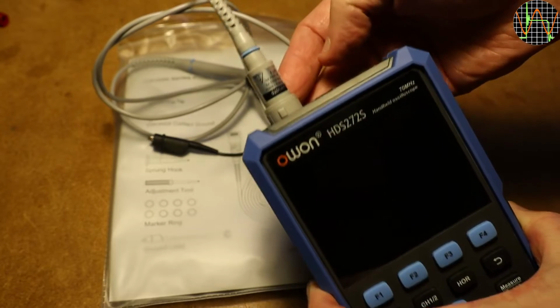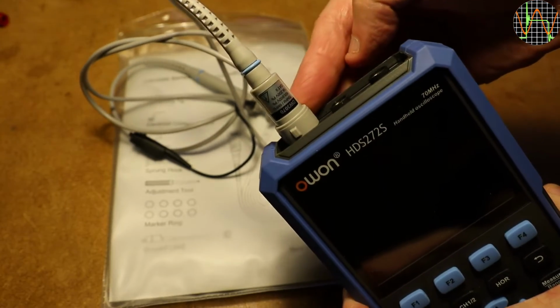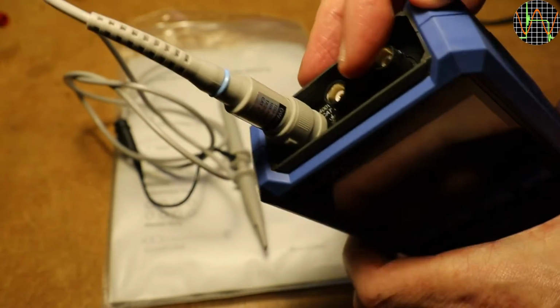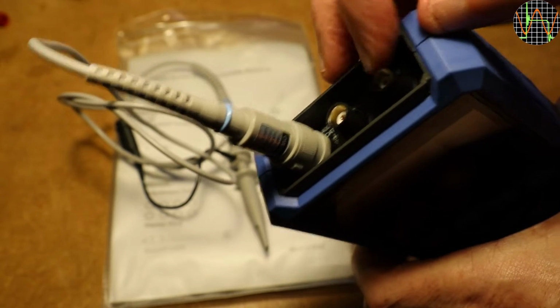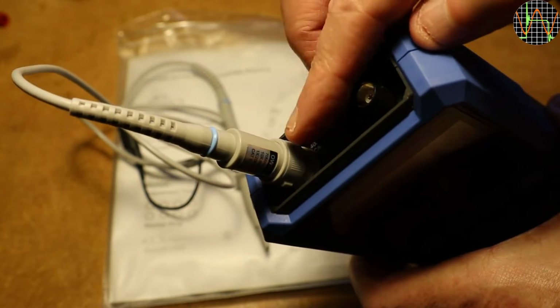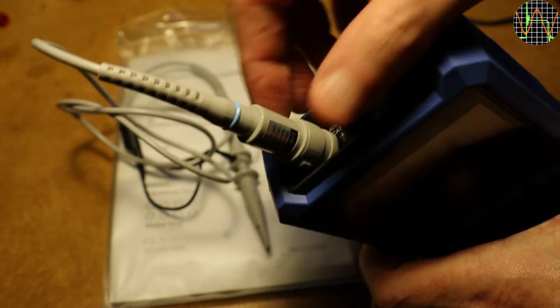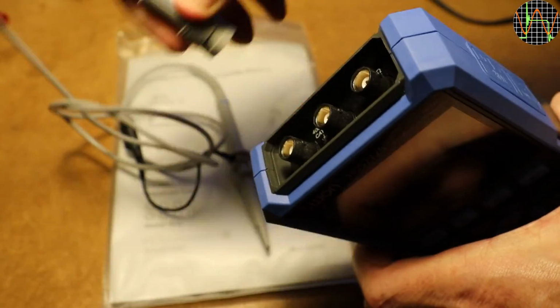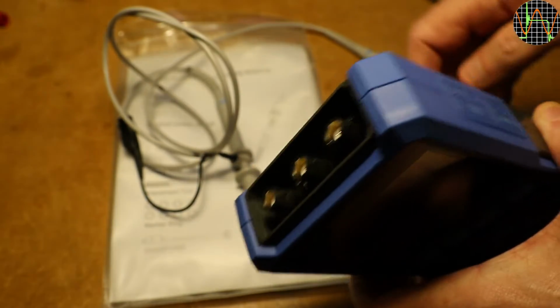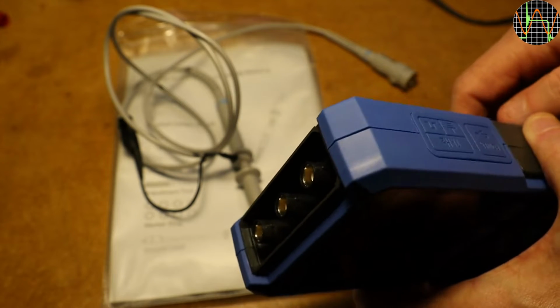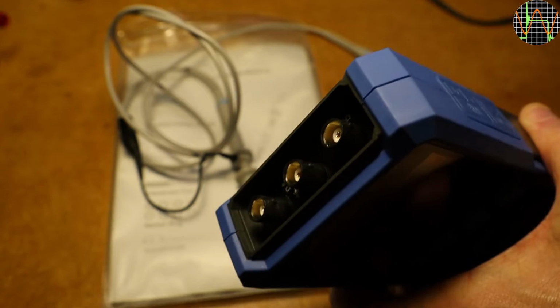The protection against touch isn't as good for the unused ports. I would have liked to see some plastic caps for those, but sadly no. In x10 mode, the probe spec says it's good for 70 MHz and 600 volts peak, which I assume stands for peak, not peak to peak — so that would be slightly more than 400 volts RMS.